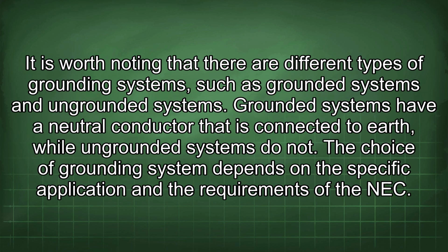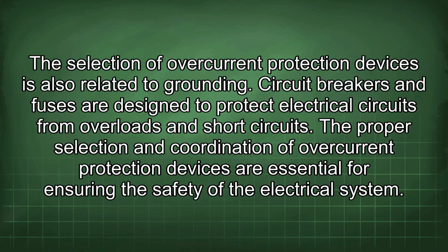It is worth noting that there are different types of grounding systems, such as grounded systems and ungrounded systems. Grounded systems have a neutral conductor that is connected to earth, while ungrounded systems do not. The choice of grounding system depends on the specific application and the requirements of the NEC. The selection of overcurrent protection devices is also related to grounding. Circuit breakers and fuses are designed to protect electrical circuits from overloads and short circuits. The proper selection and coordination of overcurrent protection devices are essential for ensuring the safety of the electrical system.